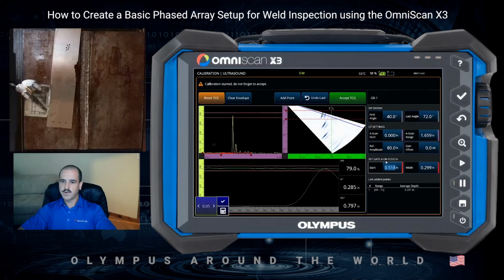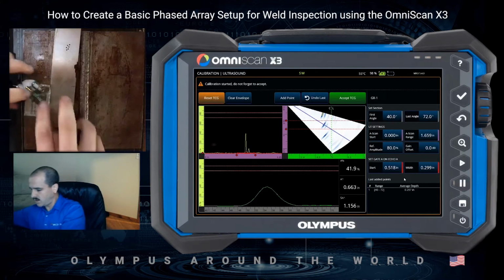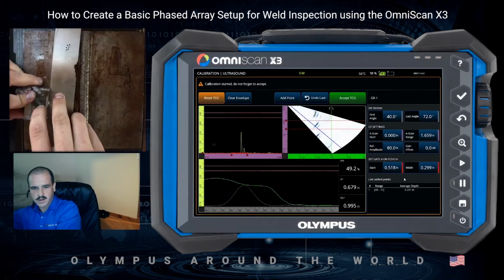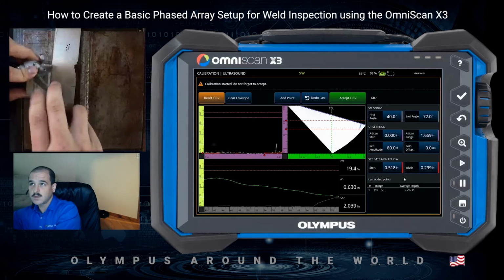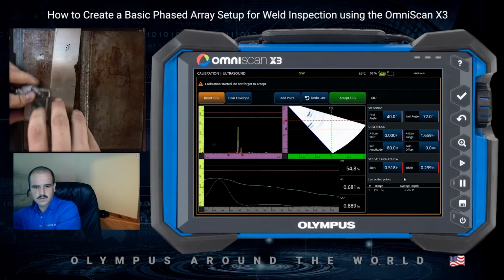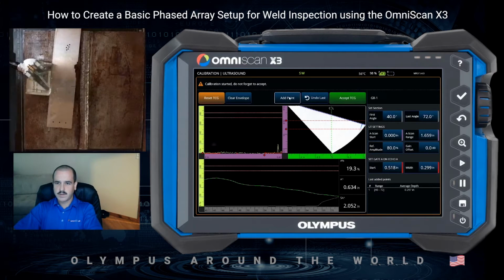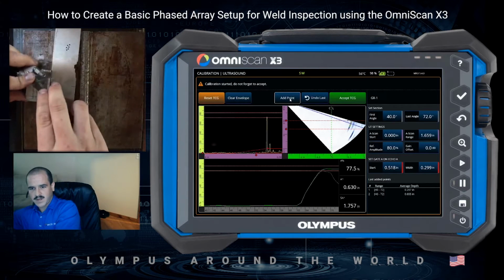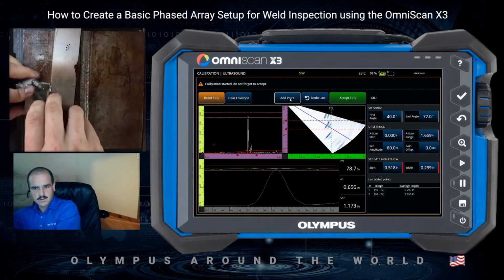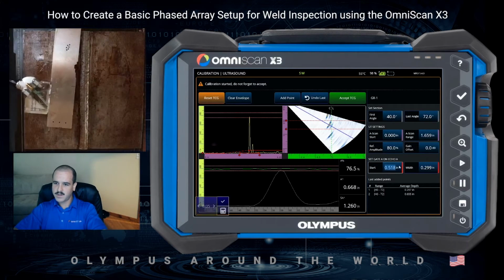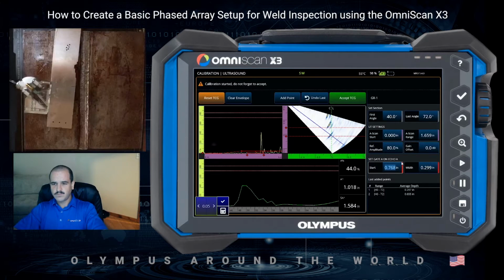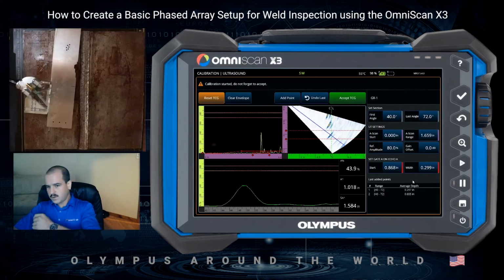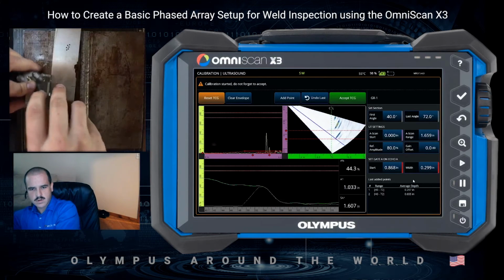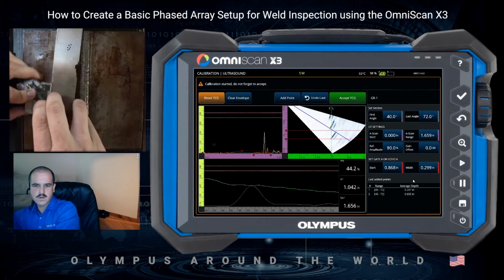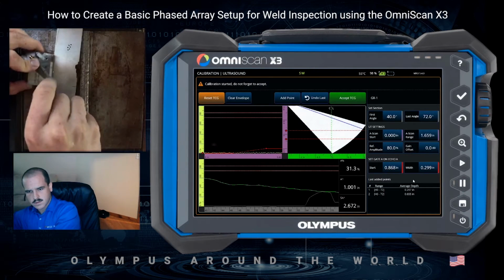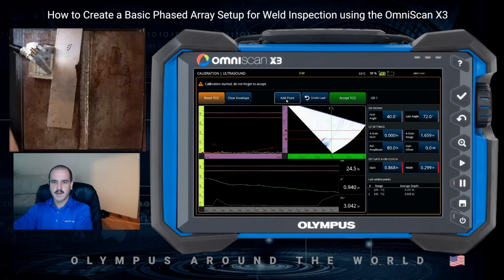All we have to do is move our gate down to the next point you want to add and do the same thing. Raster it across, get our trace peaked out the best we can. And select add point. Do a verification scan here. Looks good. We'll move on to our third and last point by adjusting the start of the gate. And perform another raster over those holes. Select add point.